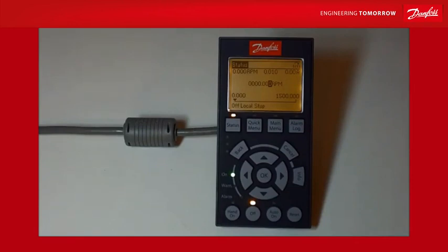Really it's just a series of tests that we can do on the motor and drive package, and it will work out resistances and reactances of the motor. It will check out the cable into the motor, and it'll also check all your phases are there and that kind of thing too. So it's a useful thing to do. Now it's not necessary. If you take the drive out of the box, it should work basically with a motor straight away. But it gives you much better performance if you do it, so it's probably well worth doing. And I'm going to just show you how to do it today.